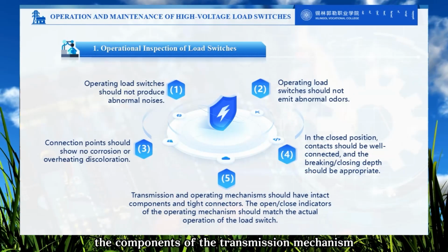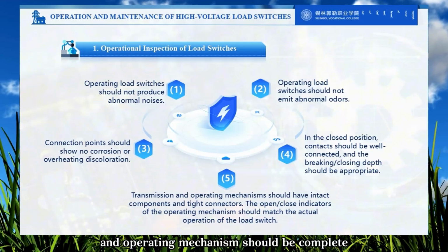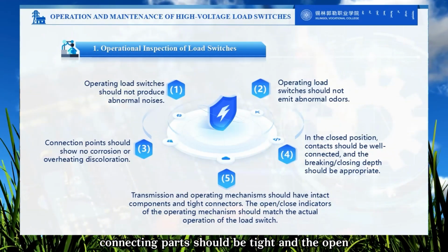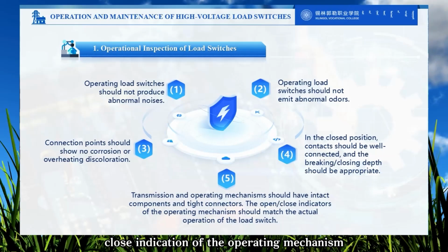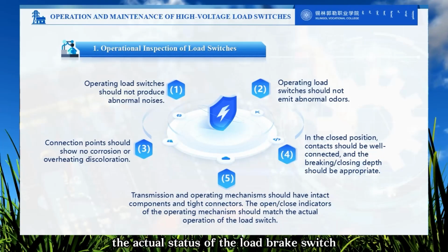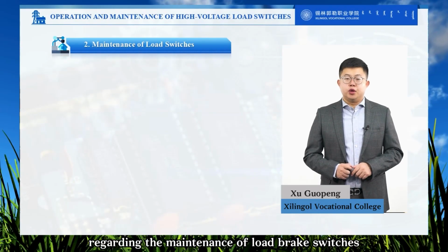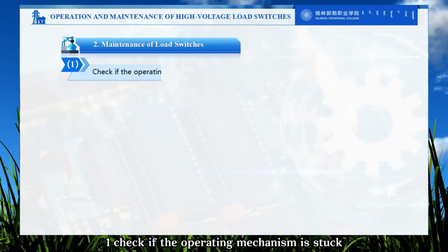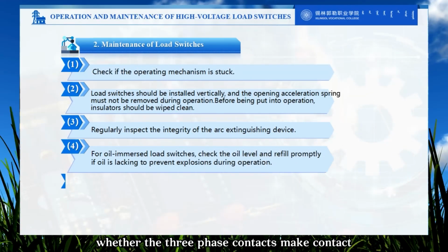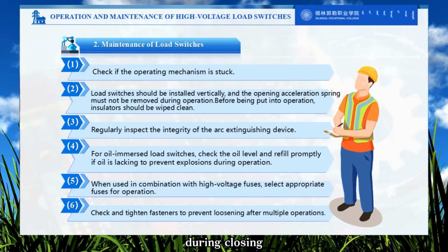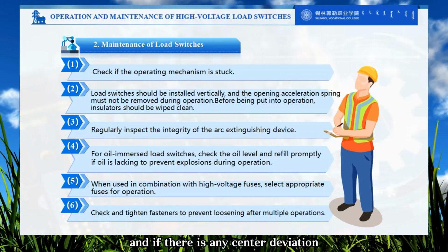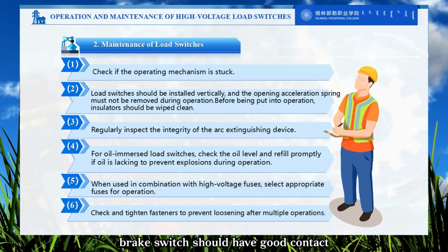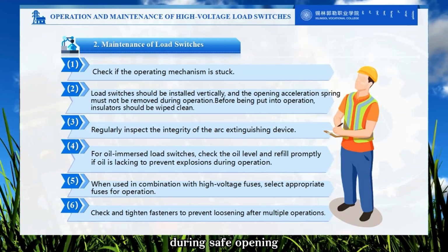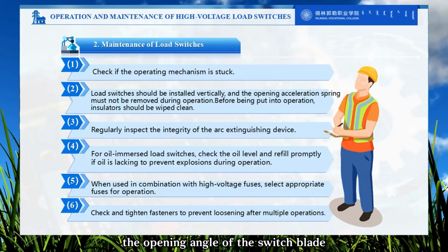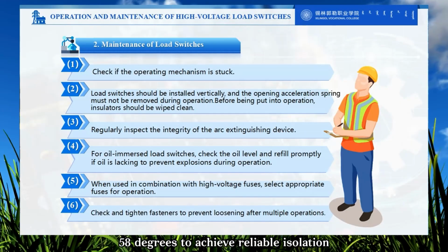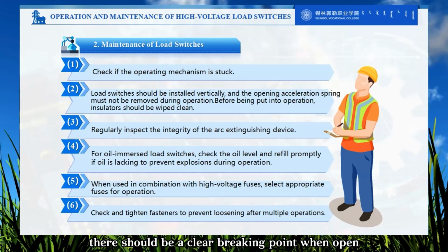5. The components of the transmission mechanism and operating mechanism should be complete. Connecting parts should be tight, and the open-close indication of the operating mechanism should match the actual status of the load break switch. Regarding the maintenance of load break switches, we need to pay attention to the following. 1. Check if the operating mechanism is stuck, whether the three-phase contacts make contact simultaneously during closing, and if there is any center deviation. The main contact of the load break switch should have good contact, with no contact overheating. During safe opening, the opening angle of the switch blade should be greater than 58 degrees to achieve reliable isolation. There should be a clear breaking point when open.